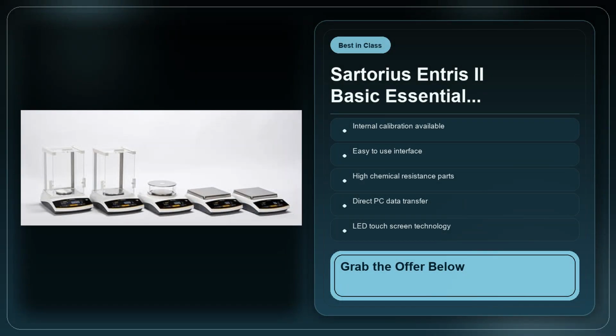That's where the Entris II's ISOCAL system and LED touch interface start to matter. The internal calibration ISOCAL is built right into the balance, which means you can trigger a calibration cycle with a single touch. In practice, this cuts down the routine that many of us used to perform with external weights. Instead of pulling out a set of calibration standards, waiting for the balance to settle, and then documenting the results, you just press a button and the system does the math for you. For a lab that runs dozens of weighings a day, that translates into minutes saved each shift, minutes that add up to hours over a month. If you're the kind of user who hates manual calibration logs, you'll appreciate that.